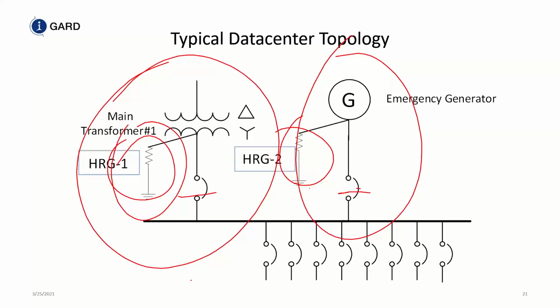Okay, so this is for the Canadian Electrical Code, right? As far as I know, it says if you employ a high resistance grounded system or any resistance grounded system, you must monitor the integrity of the resistor. I don't think they differentiate between normal and generator. So if you have a normal system, you must have monitoring for this resistor. And if you have a generator, you must have monitoring for this resistor. So I think you have to have monitoring for each resistor that's on the system, because if the generator breaker is closed, that means, well, obviously these are interlocked. You don't parallel.